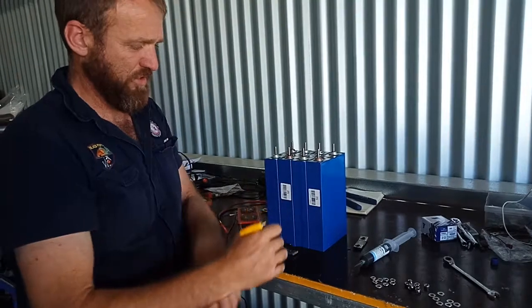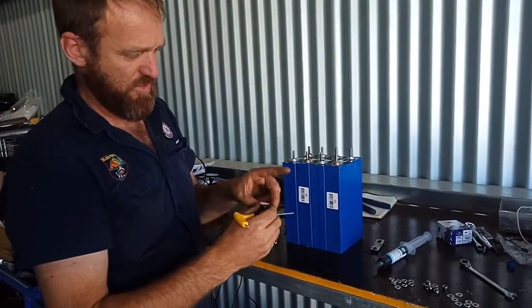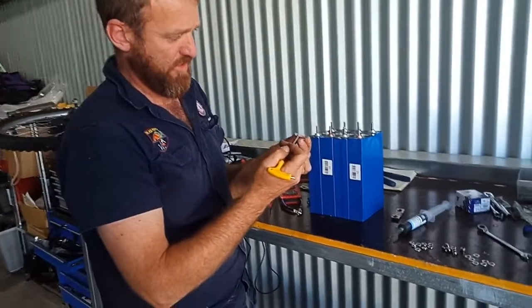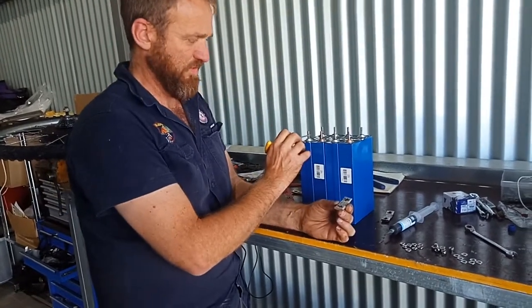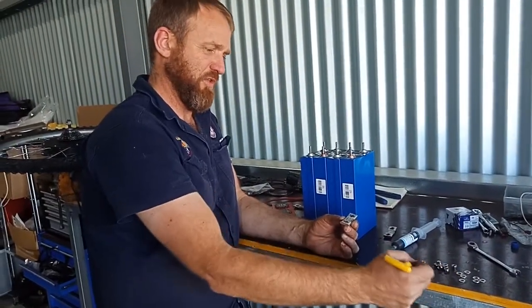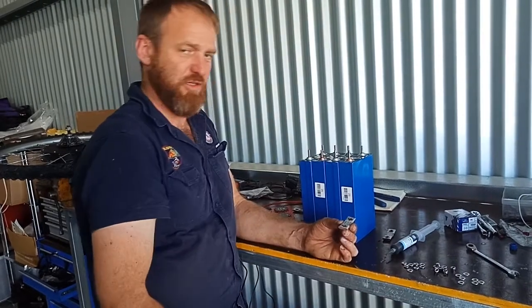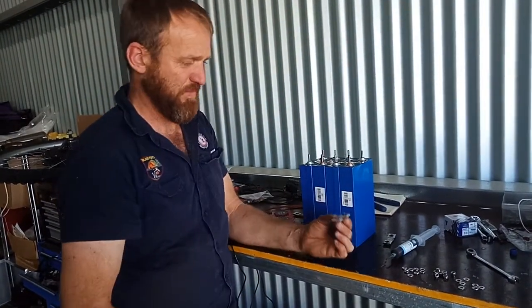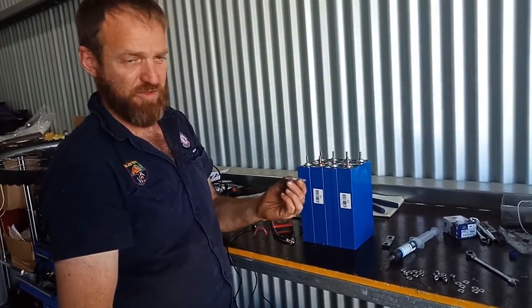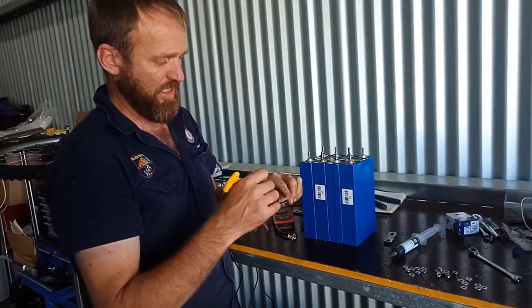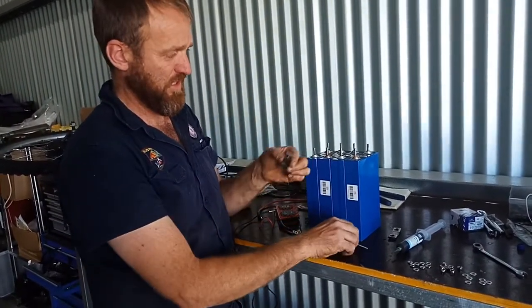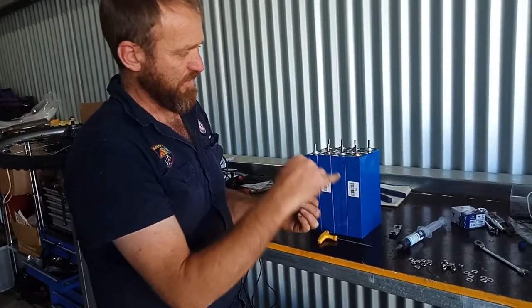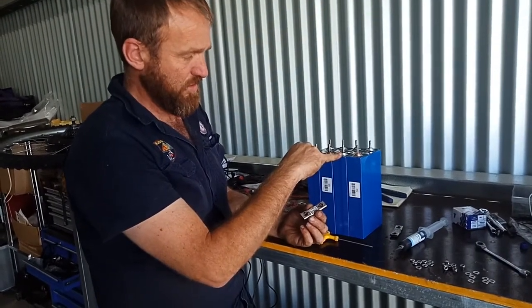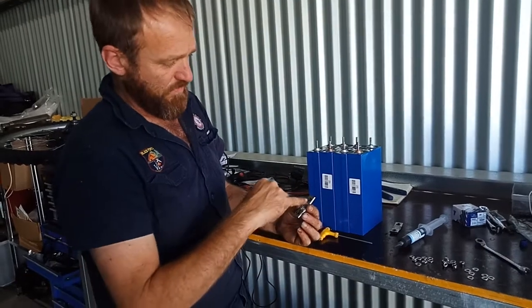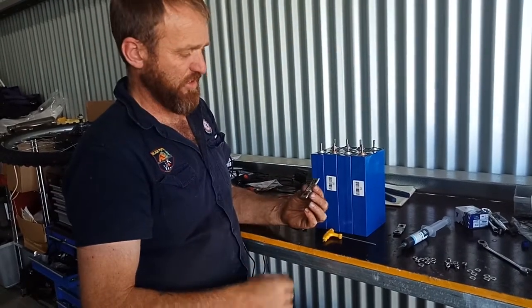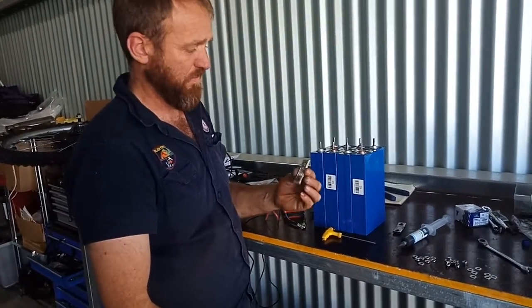I had to measure the bus bars and this distance, then combine that to get the height of these, plus a washer, spring washer, and a lock nut with 2 threads exposed, to get a sufficient tight seal and eliminate any arcing after installation. That's another reason I put on the conductive grease, to fill up the void caused by slots in the piece.